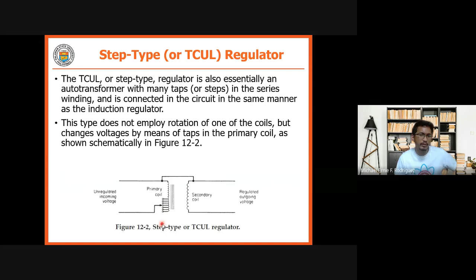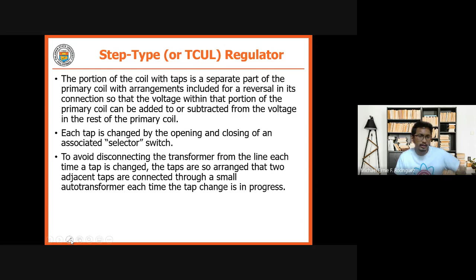Each tap is changed by opening and closing of a selector switch. To avoid disconnecting the transformer from the line each time a tap is changed, the taps are arranged so that two adjacent taps are connected through a small auto transformer each time the tap change is in progress. Kaya hindi natin kailangan i-disconnect yung transformer.